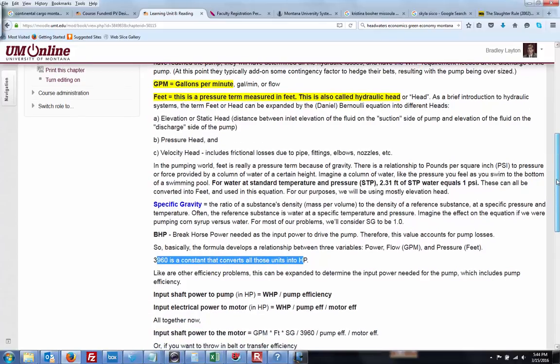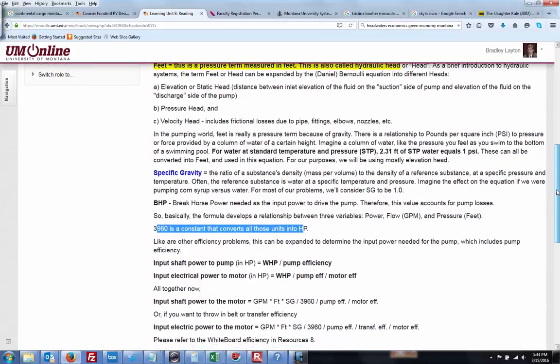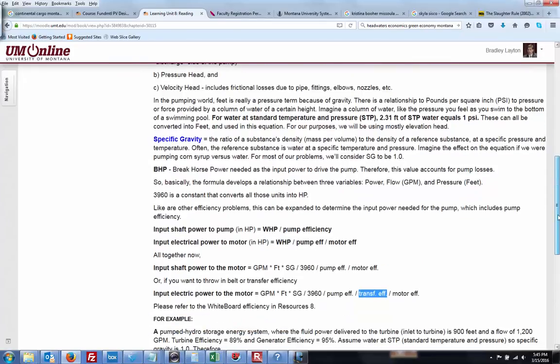Okay, input shaft power is the water horsepower divided by the efficiency. The input electrical power, you have to divide by the pump efficiency, divide by the motor efficiency. Altogether now, power to the motor is gallons per minute times the feet times the specific gravity divided by 3960, divided by the pump efficiency, divided by the motor efficiency. And then if we put in the transfer, you can have yet another efficiency metric in there. Okay.